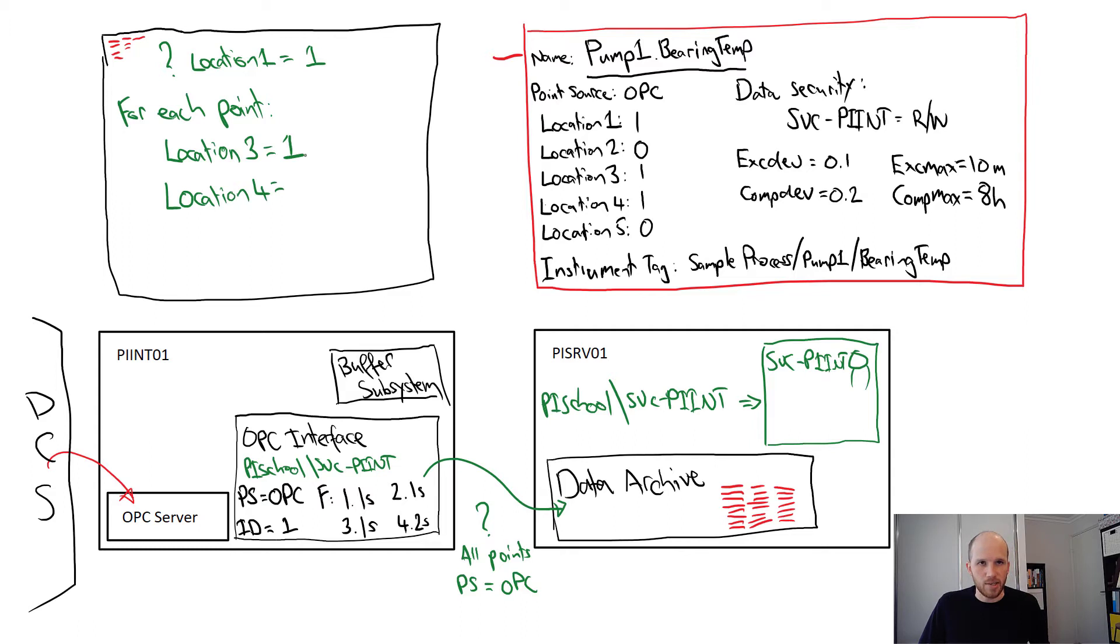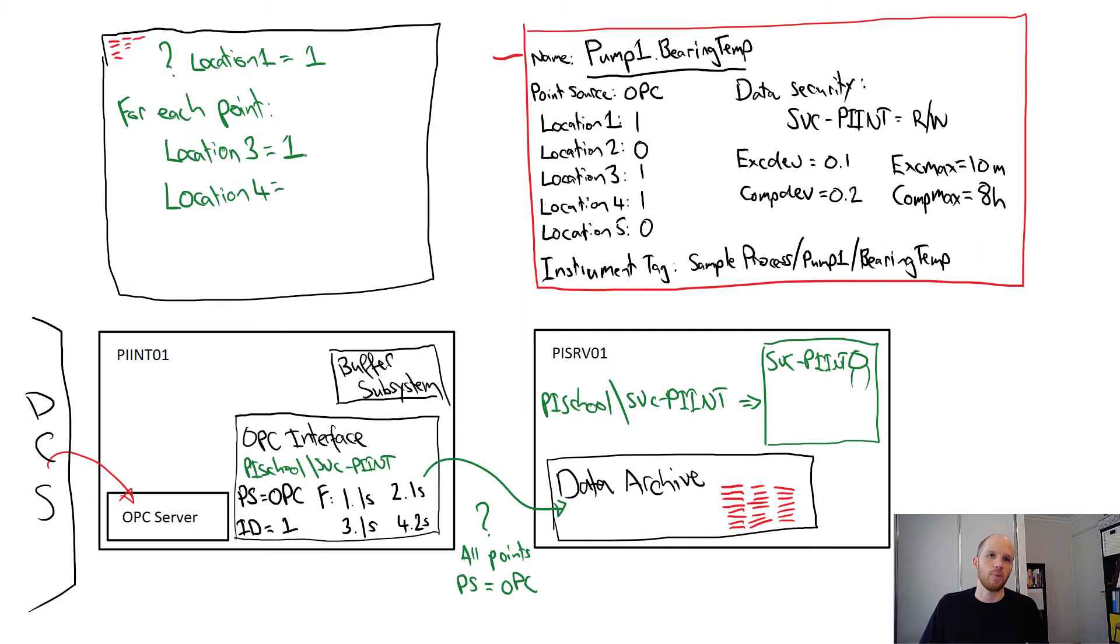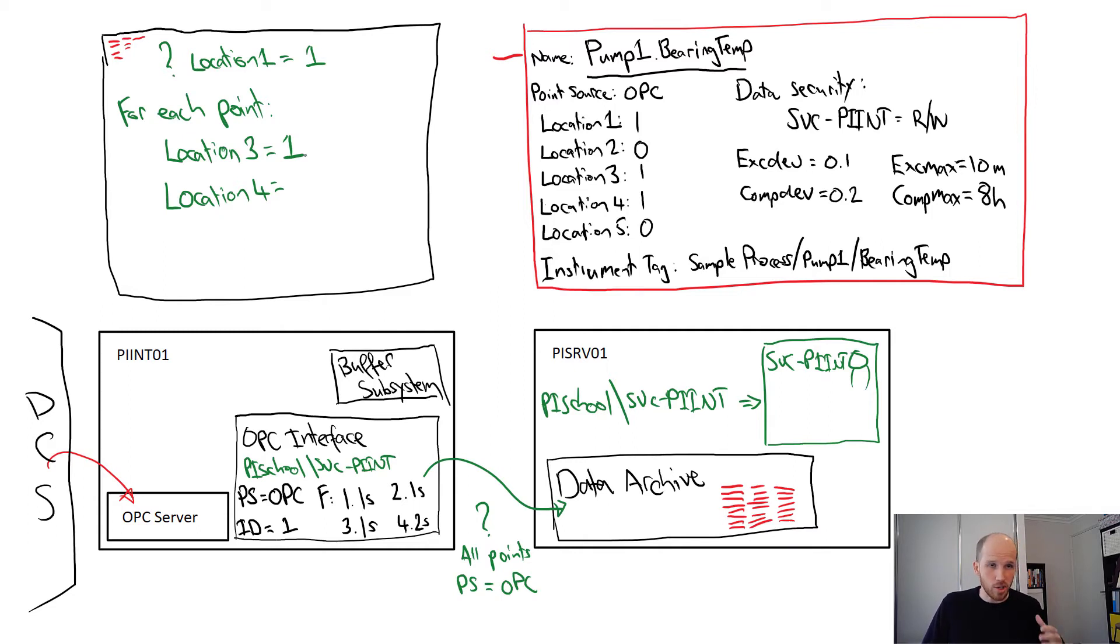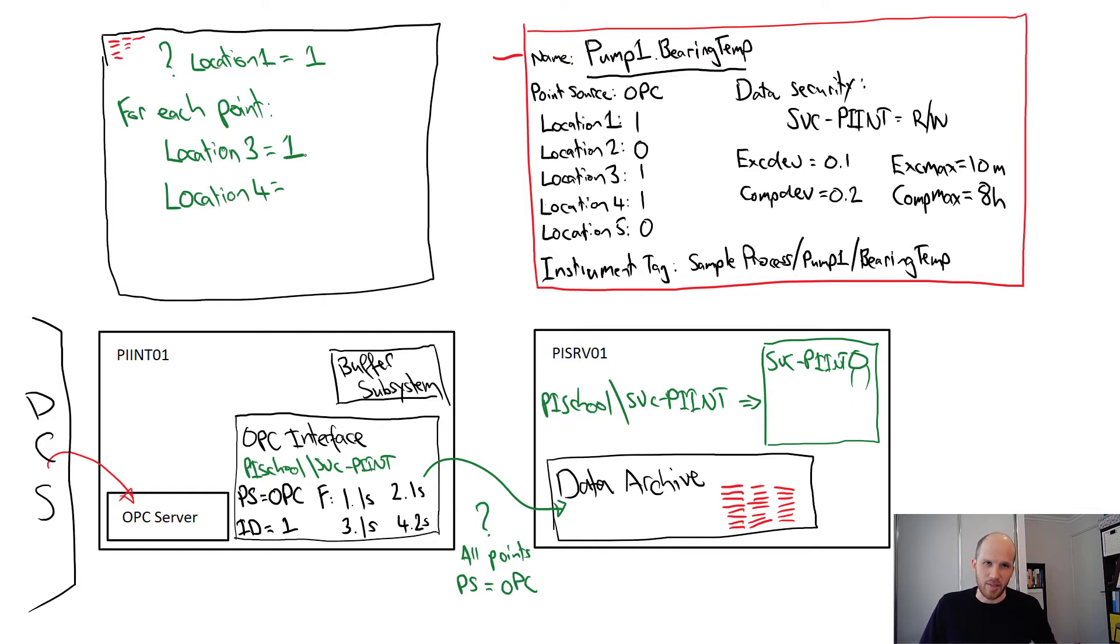This means that when the interface first makes a connection to the OPC server, it lets the server be in charge of when it sends data. If it was a poll tag, the interface would constantly poll for an update from the server at whatever we set the scan frequency to.